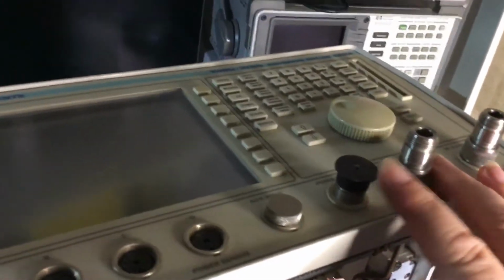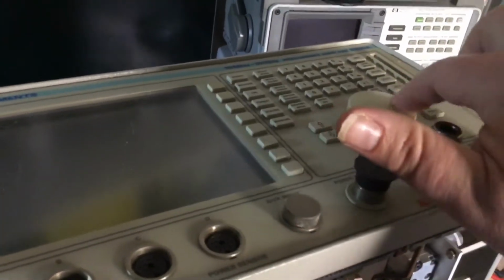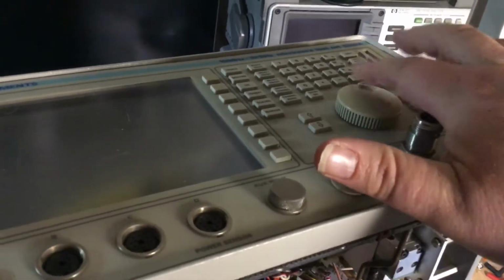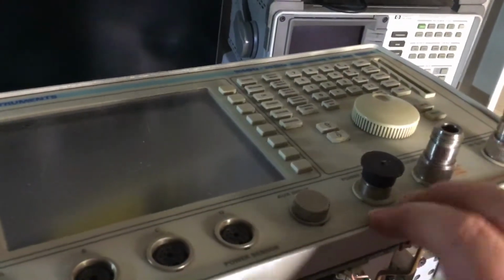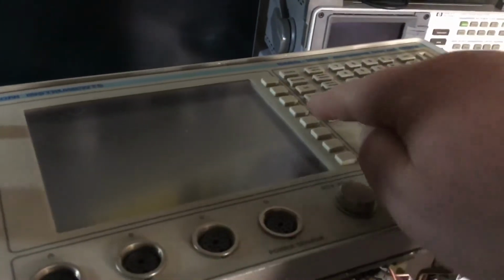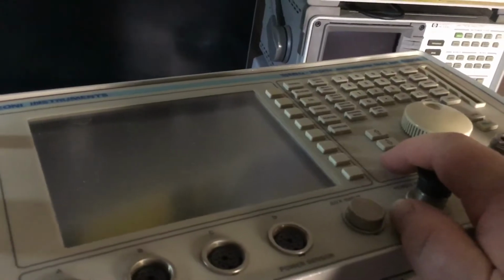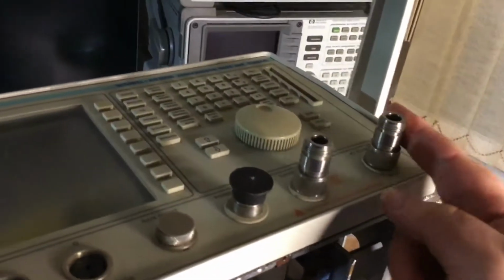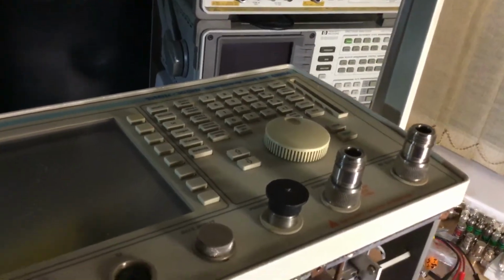This one has a fault on it where the vernier control for the RF output level doesn't work. It doesn't matter what level is shown on the screen and what you set on the output power, the signal from the signal generator output doesn't give the correct level.